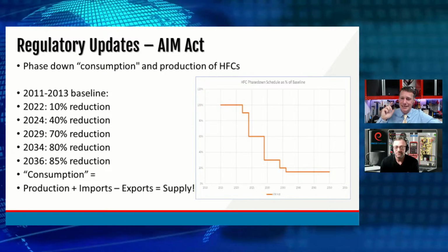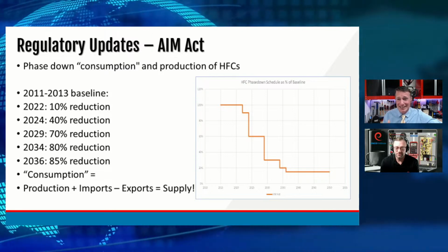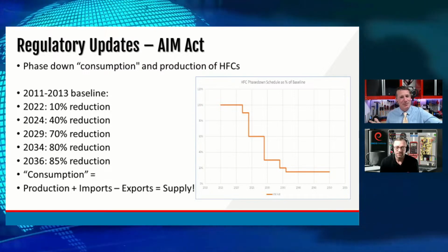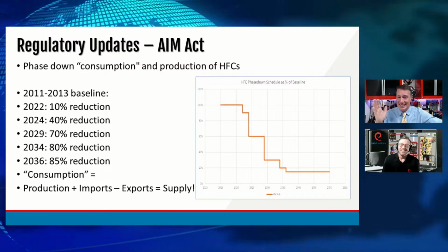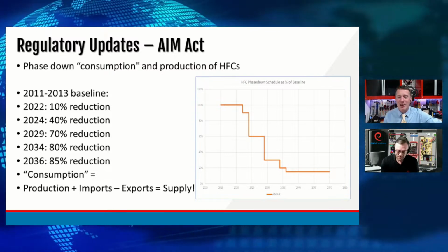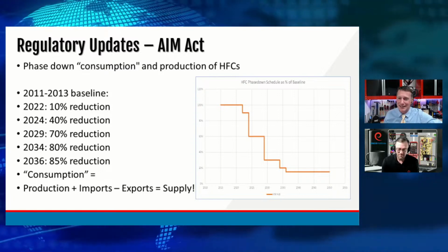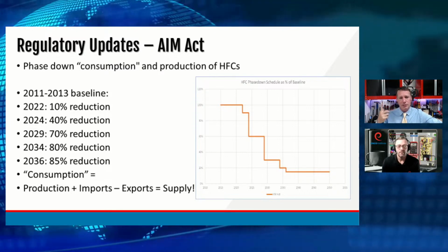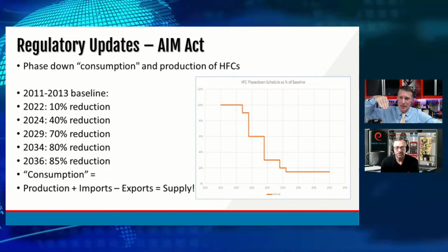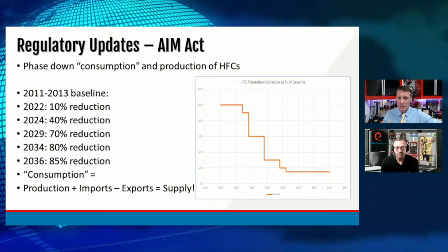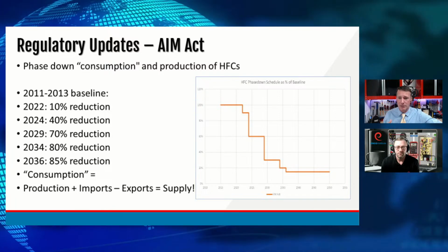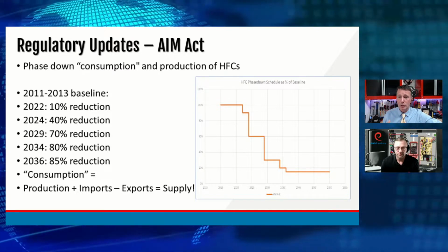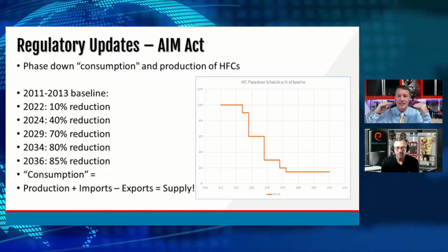Anyone in the crowd see the prices of R410A, R404, R134A? Did you see the prices of any of those go up this last year by chance? I see it on forums all the time, and every once in a while I'll put a reply and people treat me like I'm some maniac just coming up with this stuff. But this is the truth. On January 1st of 2022, we started a 10% reduction down our slide, which means if we made 1 million pounds of an HFC refrigerant in 2021, we made 900,000 pounds of it in 2022.